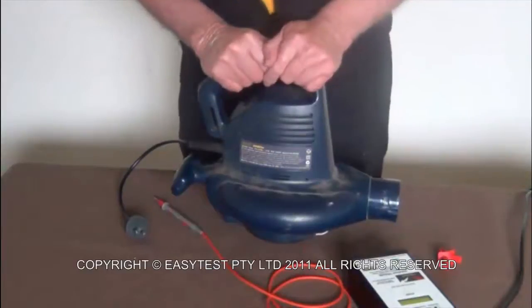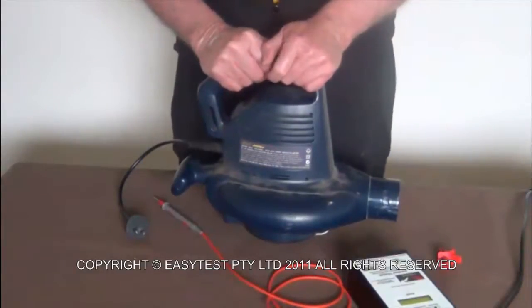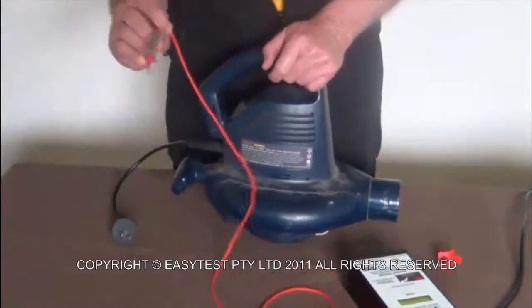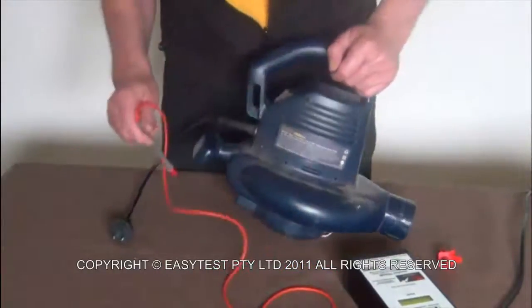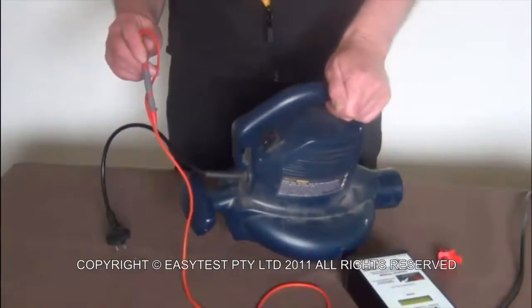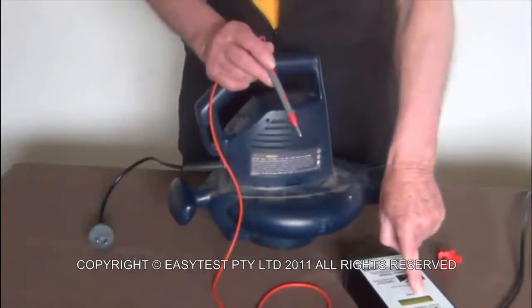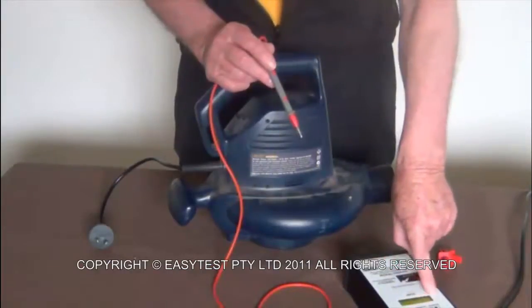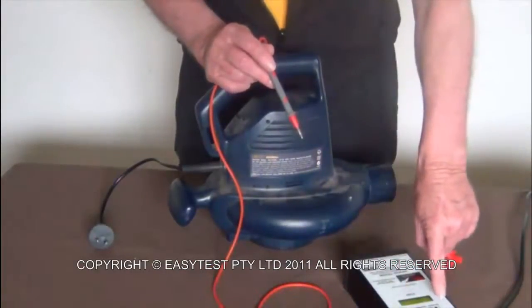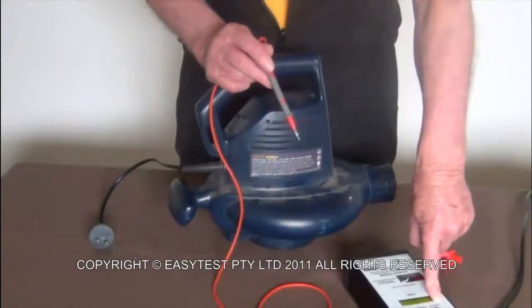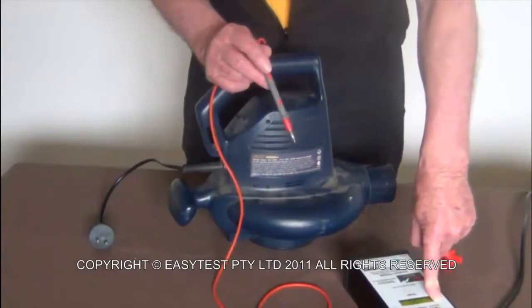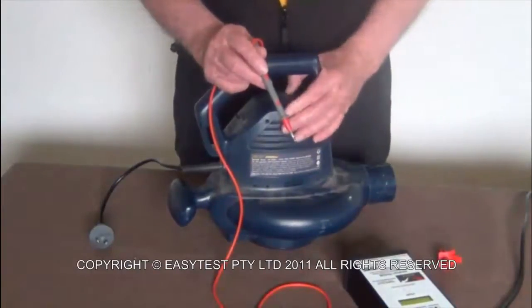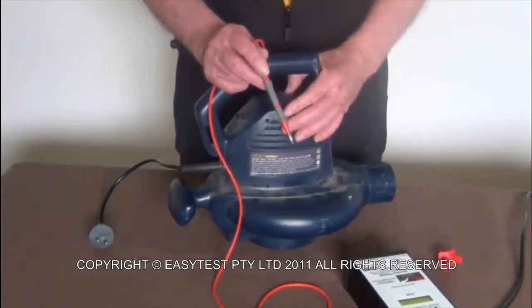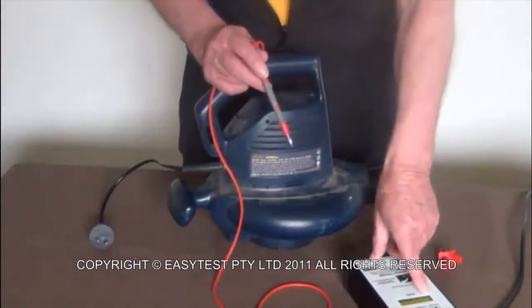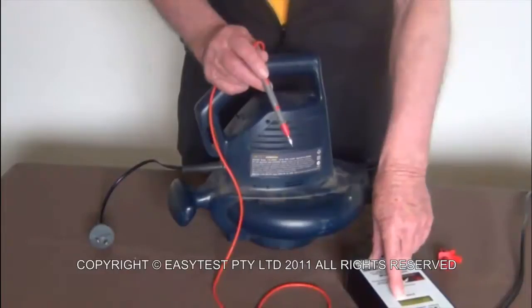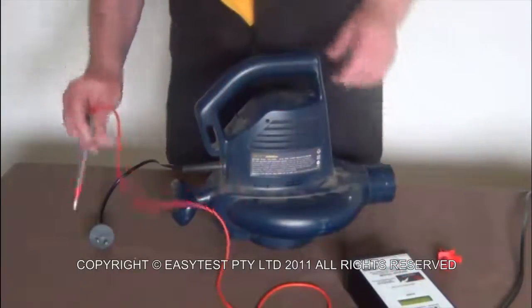And to test it, surprise, surprise, it is exactly the same as everything else. You take your probe, you touch it to any exposed metal, and you run the equipment, and you look at the earth leakage scale on your meter. When you look at this, you'll see the top line is Class 1 earth. This doesn't have an earth, it isn't Class 1, it's Class 2, therefore you simply ignore the top line and read off the Class 1, Class 2 earth leakage scale.